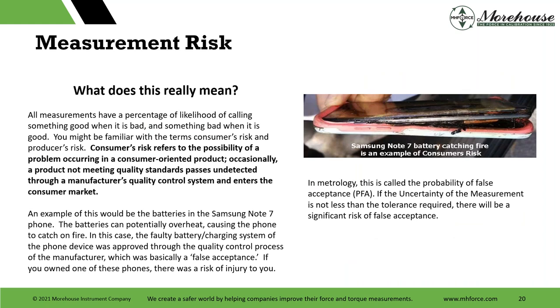Starting to talk about measurement risk a little bit — a lot of people might remember the Samsung Note 7, which was a big deal a while ago. If we look at this and start talking about measurement risk, that gets into conformity assessment, and then conformity assessment gets into all these fun words like PFA — probability of false accept — FAR — false accept risk — unconditional PFA, conditional PFA, and PFR — probability of false reject.